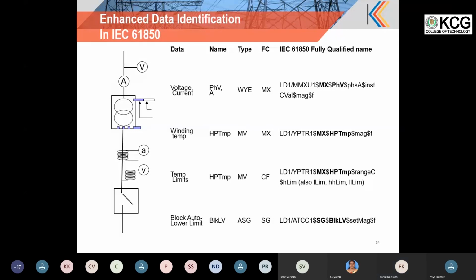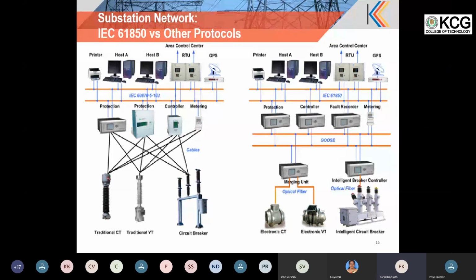This is a comparison of an earlier substation and a modern 61850 substation, given on the right side. In the earlier substation, all the CT, VT and circuit breakers have hardwiring to the IEDs or relays, from multiple vendors, and from there you can have multiple mechanisms like serial, Ethernet, any mechanism for communication. But in 61850, there will be high-end CTs and VTs with a merging unit available, and this can have an intelligent circuit breaker. Everything is connected together over the Ethernet and can have multiple communications for the process bus, station bus and inter-bay bus. All this communication happens over the Ethernet. That is a modern 61850 substation.